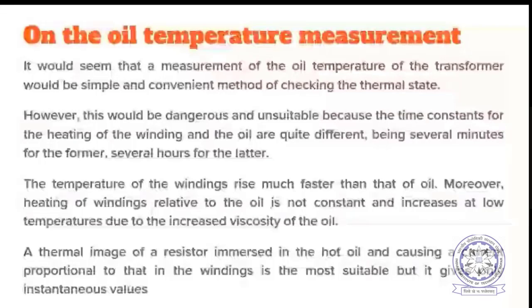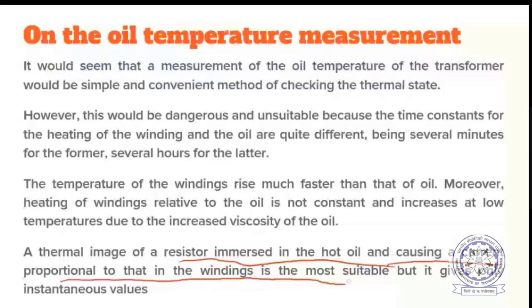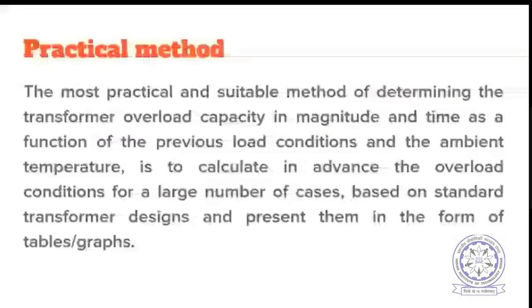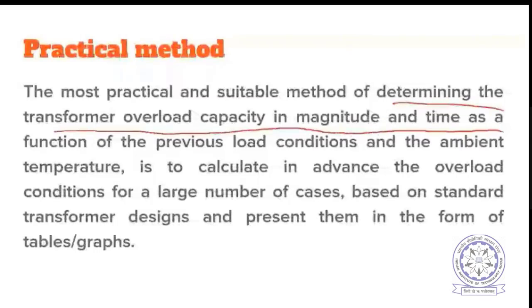So, a thermal image of a resistor immersed in the hot oil, which carries a current proportional to that in the windings, is most suitable, but it gives only instantaneous values. This was what was told just now. But the most practical and suitable method is determining the transformer overload capacity in magnitude and time as a function of the previous load conditions and the ambient temperature.